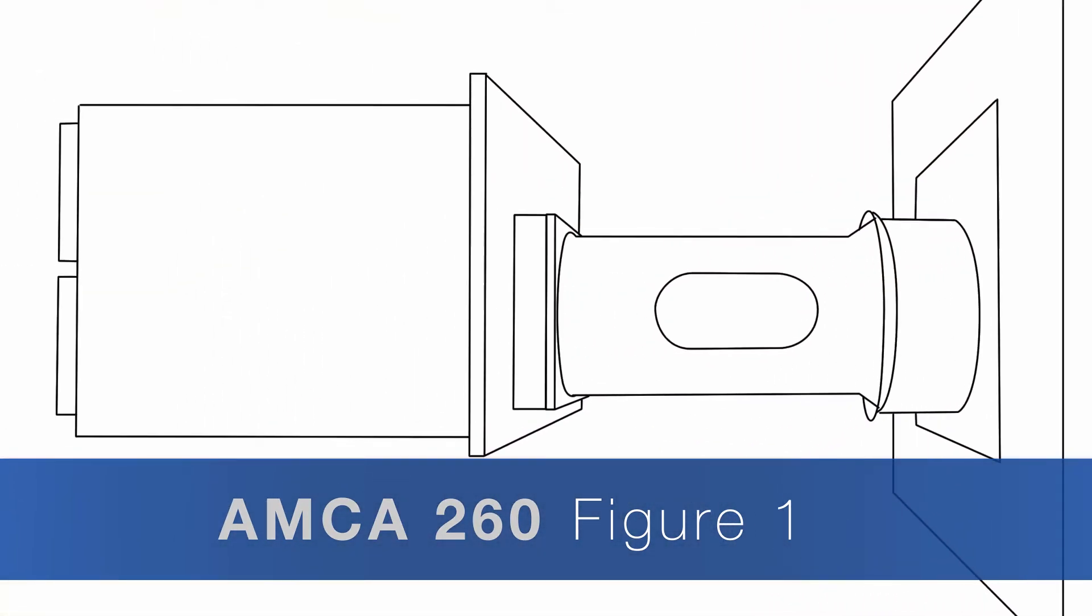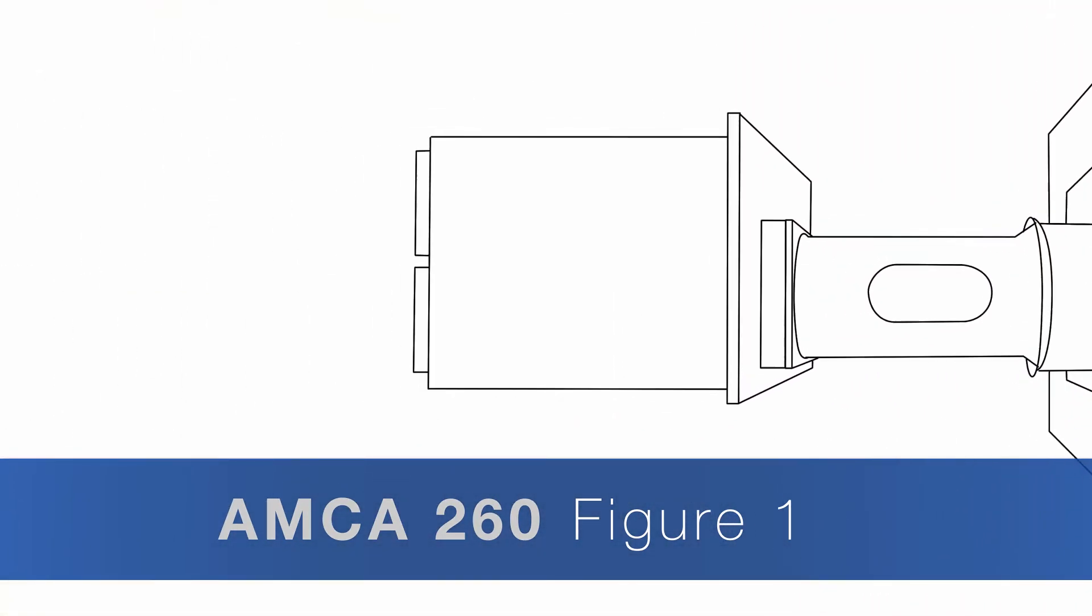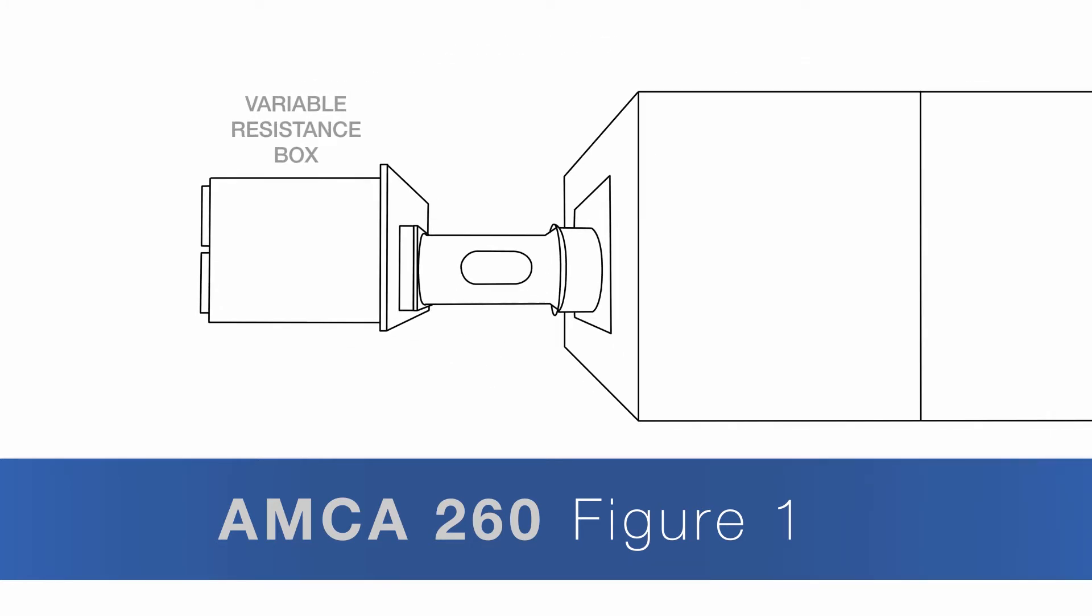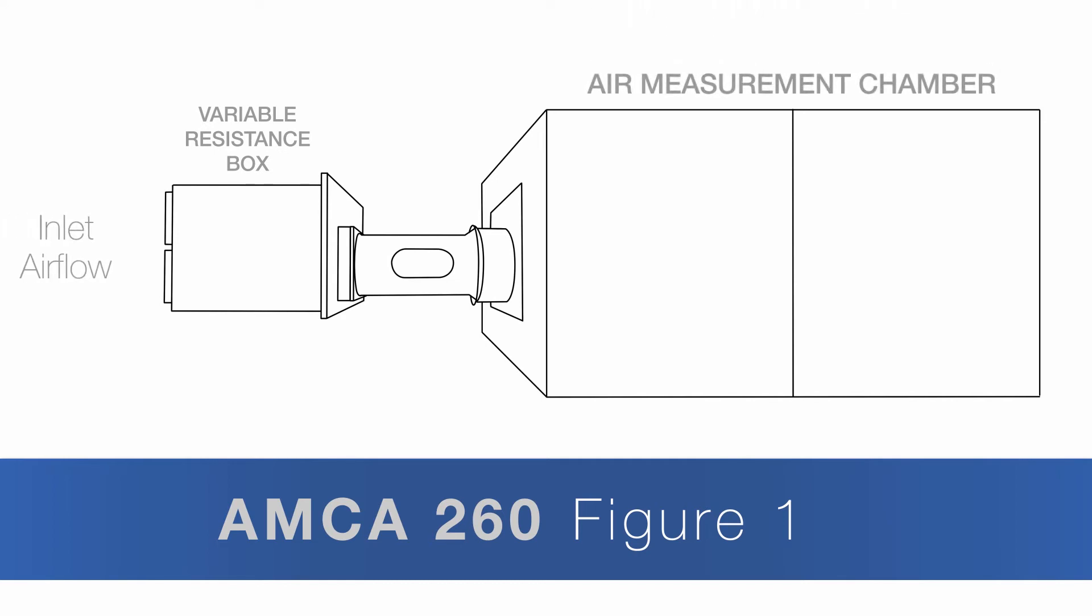The induced air fan is positioned after a variable resistance box that creates identical inlet air flows by matching pressures from the previous AMCA 210 test while the discharge of the fan is connected to the air measurement chamber.